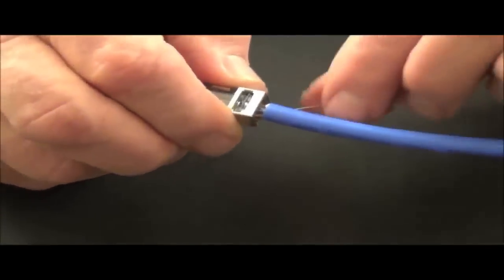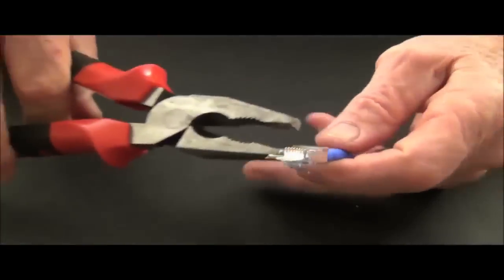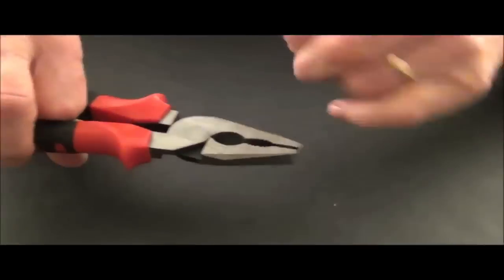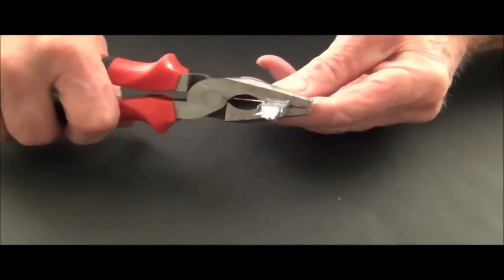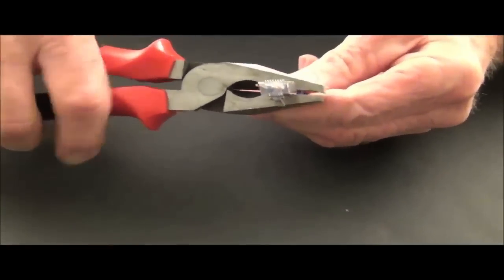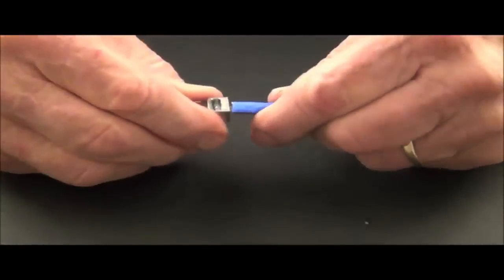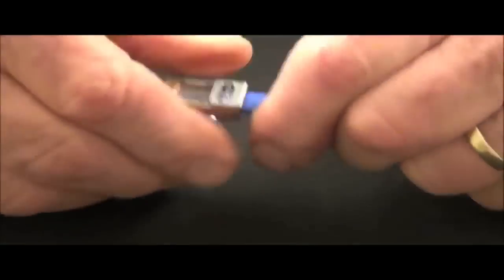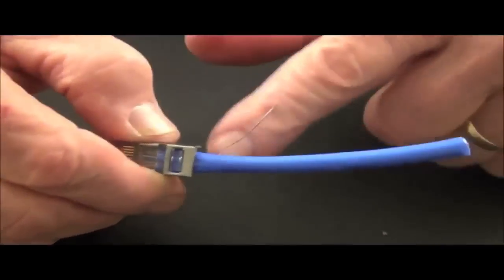So a little trick to help us here is to use the oval part of my pliers. I'm going to use this part of the tool, and not real hard, but I'm going to shape it to ovalize it so it enters the back end a lot easier. That does not take away from certification. So once I've done that, now I can put it in there. I'm going to continue to set it and then I'm going to fix the wire at the back end which is going to be my ground.